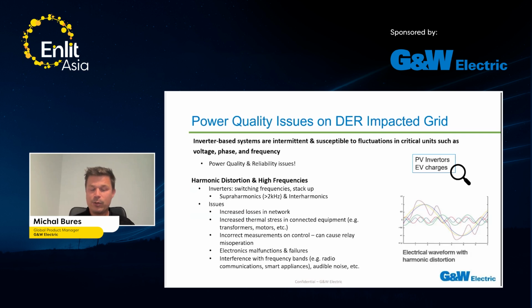So what are the issues? Just to repeat, we can have increased losses in the network. We can have increased thermal stress in connected equipment, in transformers and motors, which reduces the lifetime, and this equipment is very expensive. We can have incorrect measurement on the control units, which can cause relay misoperation, which is critical if there is some fault in the grid, which can harm persons or the environment. We can have electronics malfunctions and failures, and interference with other electronics, which is also not what we would like to see in the grid.